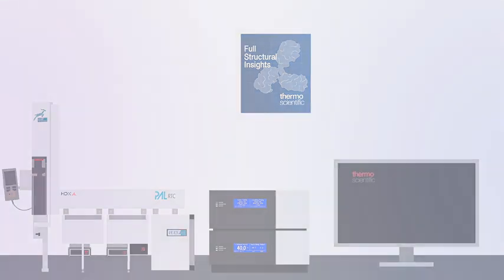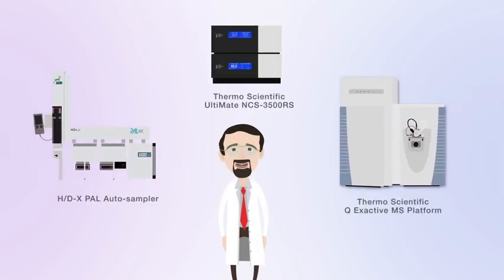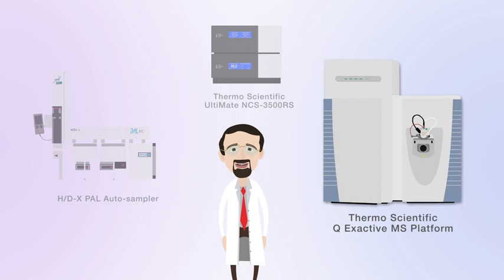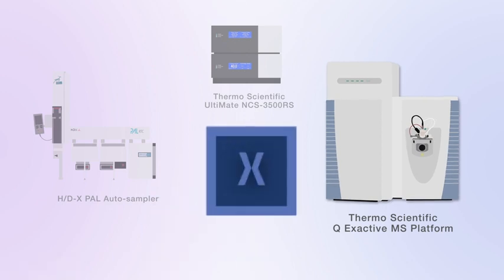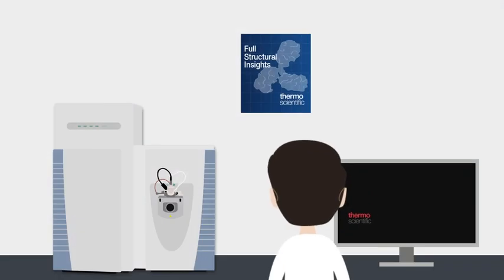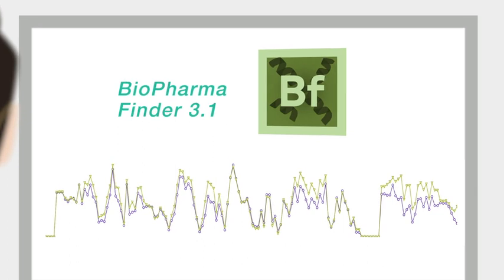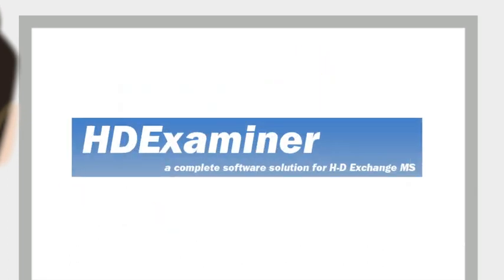The HDX PAL and LC modules integrate with any Thermo Scientific Orbitrap-based mass spectrometry system, allowing for a single software control of the entire LC-MS system, giving you choice in experimental features whilst meeting a range of budgets. Flexible software tools are provided which include Biopharma Finder software for peptide mapping, and HD Examiner from Sierra Analytics for interpretation and visualization of deuterium uptake.